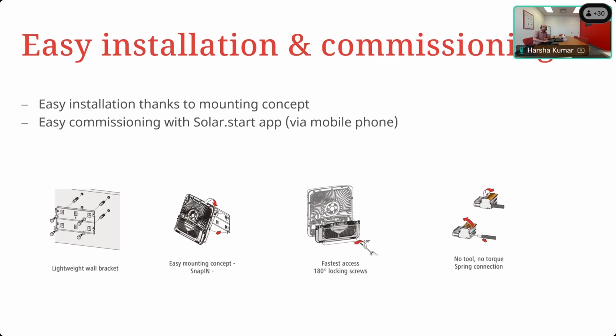Since there is no display anymore, if you need to commission the device, you activate the access point on the inverter, then connect to that access point using a smart device, just like with the data manager. It could be a smartphone, tablet, or laptop. Then you can choose to use the Solar Start app—again, you don't need to pay for it or sign up, you can just download and use it without signing in—or you could use the same web interface as with the data manager, since we've kept the IP address the same. So you activate the access point, connect with your smart device, and bring up either the app or the web page using the IP address, same as with the data manager.